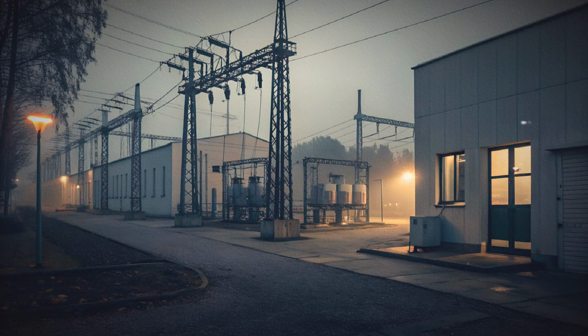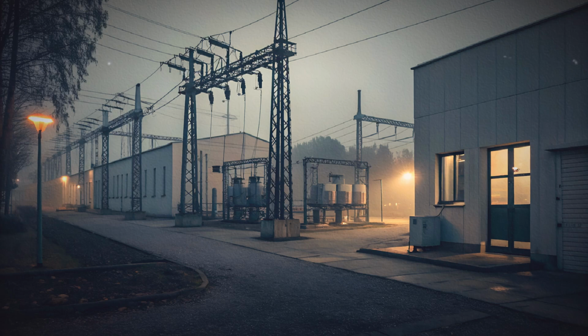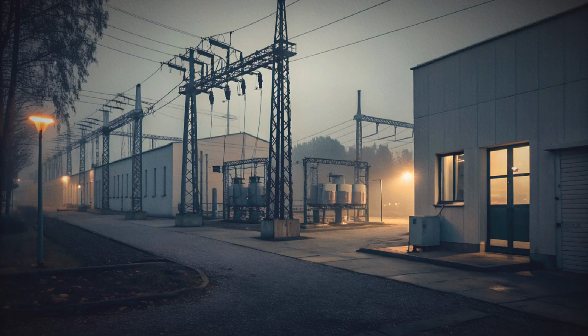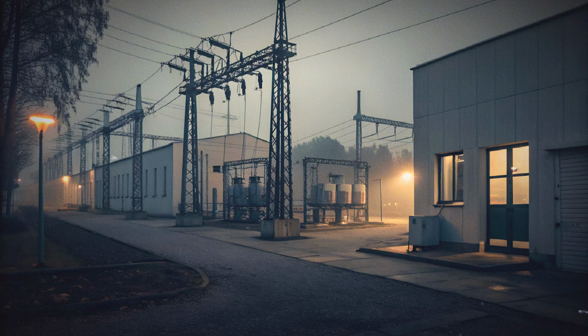Protection systems detect abnormal conditions and act to isolate faults. Protective relays monitor currents, voltages, and other parameters. When a relay detects a fault, it sends a trip signal to circuit breakers. This isolates the affected equipment or line. The response prevents equipment damage and limits the area affected by a fault. Instrument transformers, such as current transformers and potential transformers, provide scaled-down signals to relays and meters. These measurement devices enable accurate monitoring and protection without exposing sensitive equipment directly to the high voltages present on the primary side.